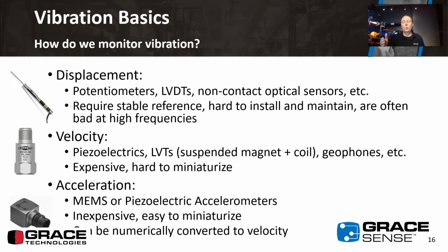So what we typically use in a vibration monitoring application is an accelerometer. These MEMS or piezoelectric-based transducers are inexpensive, easy to make, and pretty small. And they allow us to capture acceleration data, which can then be numerically integrated and converted into a velocity measurement or a displacement measurement. So this is what really lets us get at that balance of plant application, where we're using low-cost sensors to get sensing capabilities on maybe all of the bearings in our facility.